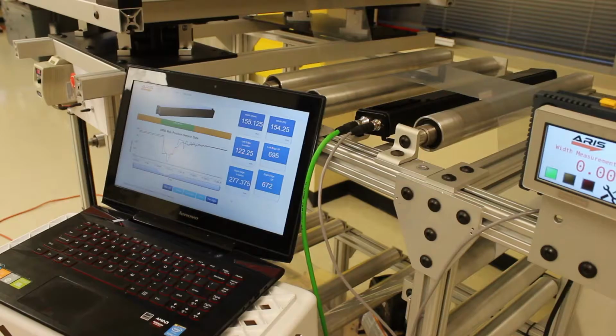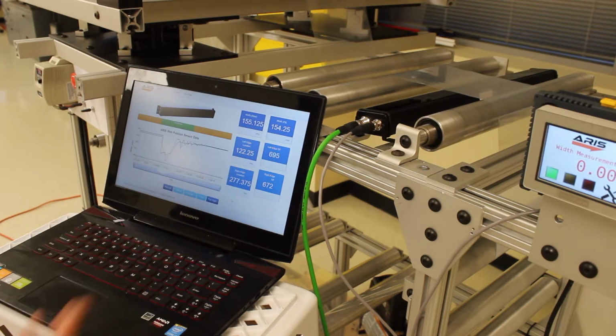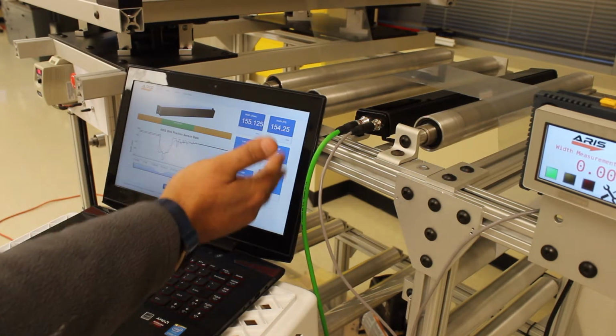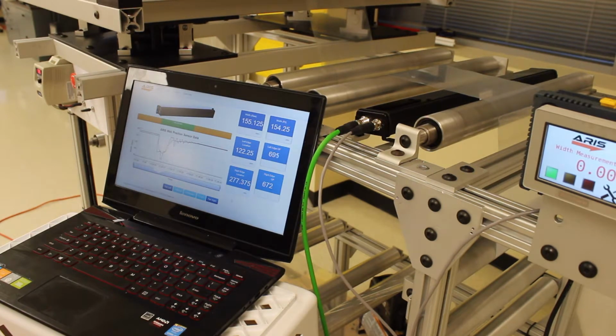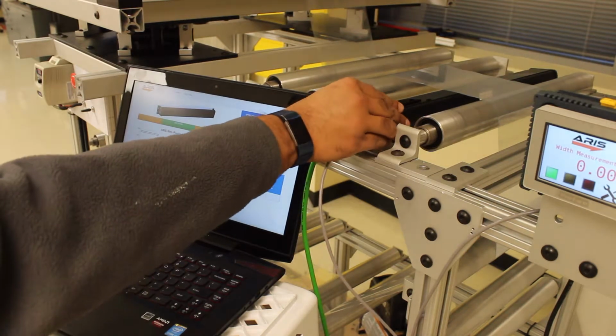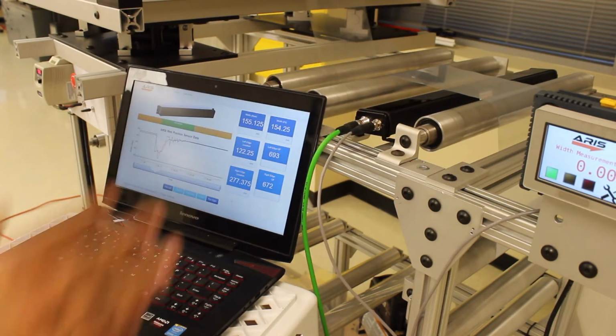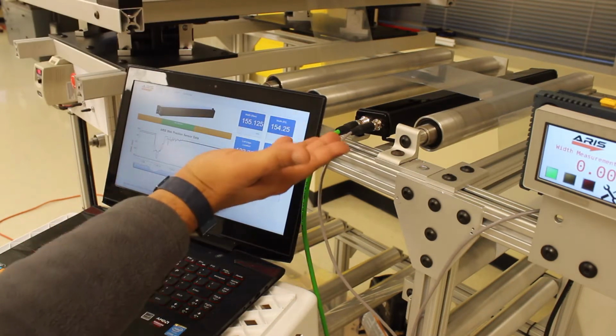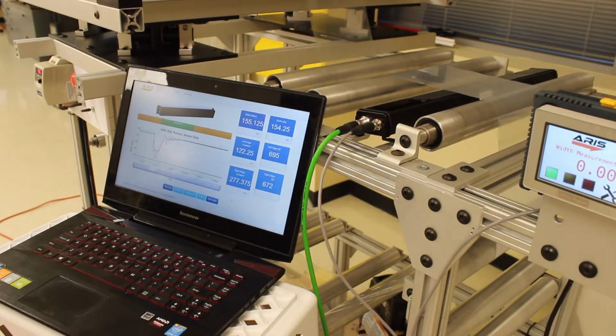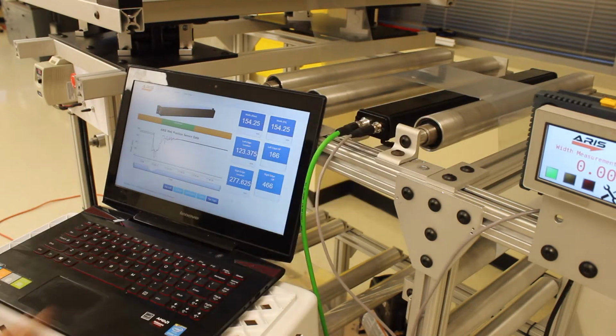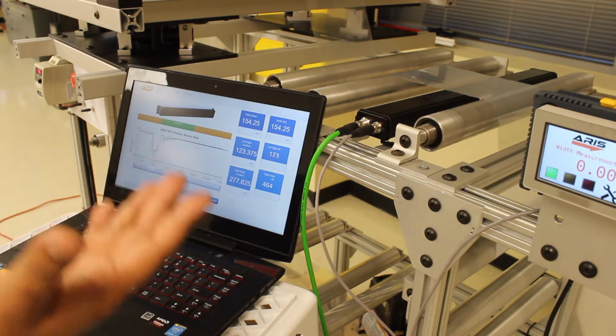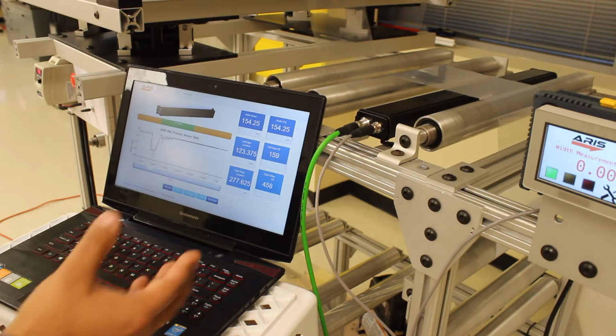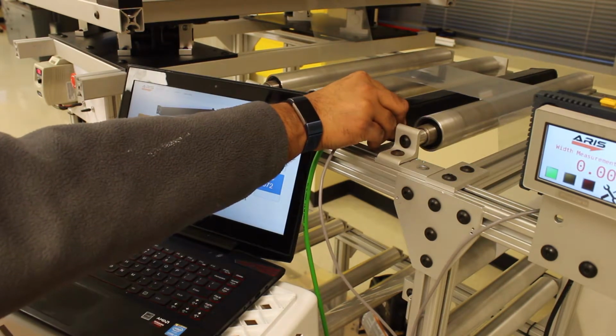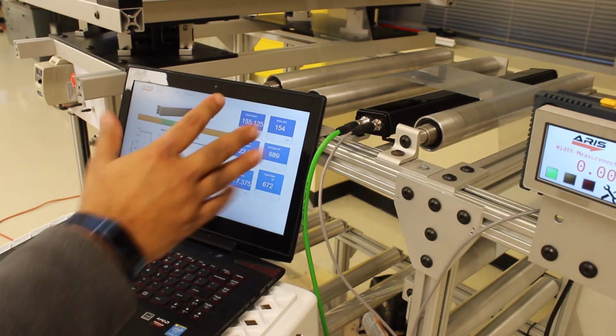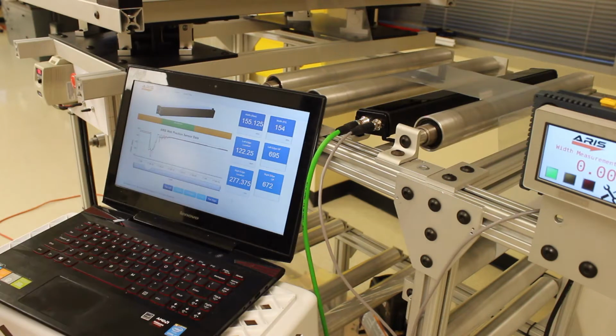All of these are shown here. So the main thing that we want to do is make sure that the quality factor on both edges is pretty high. And as we mentioned before, one of the things that improves the scattering is angling the sensor. Either we can lift this roller up or angle the sensor so that we get a pretty good quality factor. If you notice, when I move that, since we don't get a good scattering, the quality factor went down. But if we install the sensor at about a 15 degree angle, then we get a pretty good quality factor signal, and then you get the measurement there.